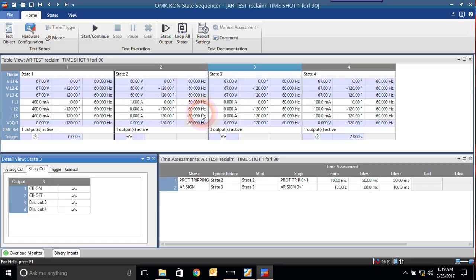Here we have something different from the other relays. Other relays have a waiting time for synchro. If this waiting time passes, synchro goes to lockout. This function does not. If synchro is not okay, it will hold and freeze until this condition is gone. If this condition is gone, it will complete its sequence; otherwise it will still hold. Okay, this is the difference between it and the other relays. If you want to go to lockout or something, you can program this from FlexLogic. You can make your function, make your logic, and add more effect on this function according to your understanding of this function and the required logic.